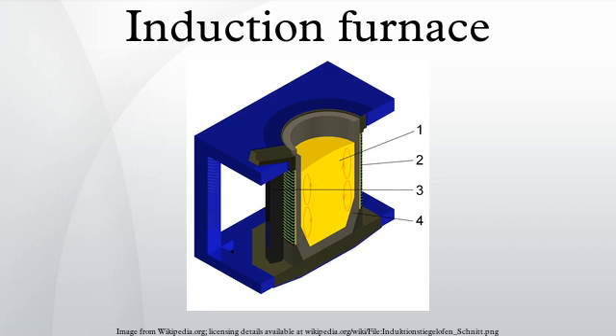A preheated, one-ton furnace melting iron can melt cold charge to tapping readiness within an hour. Power supplies range from 10 kW to 42 MW, with melt sizes of 20 kg to 65 tons of metal respectively.